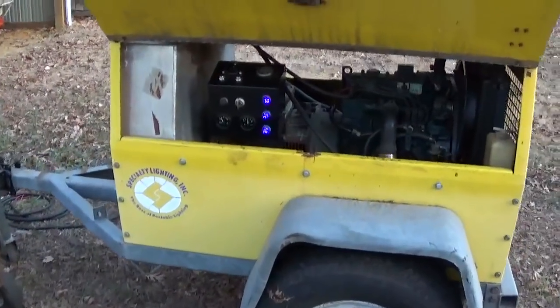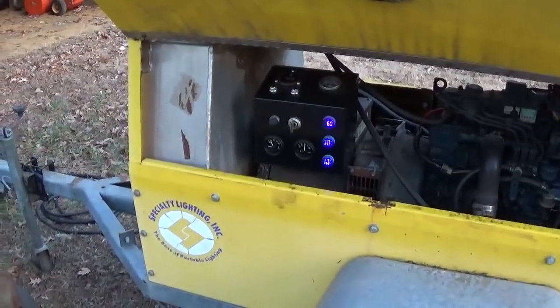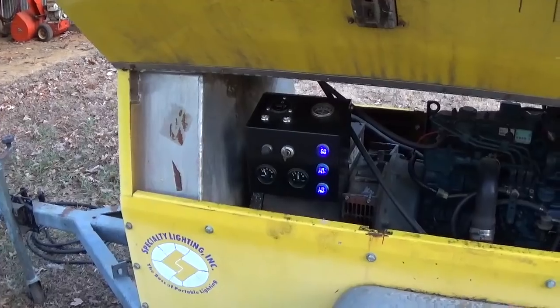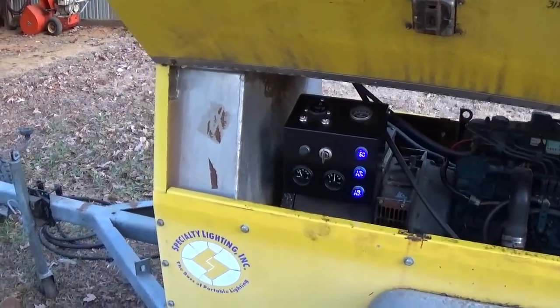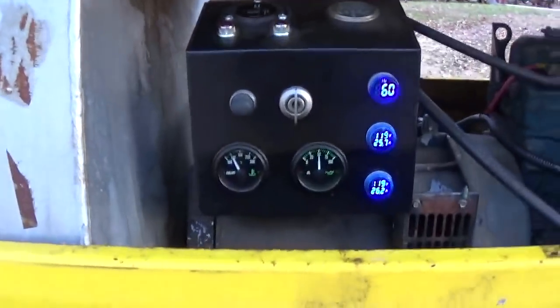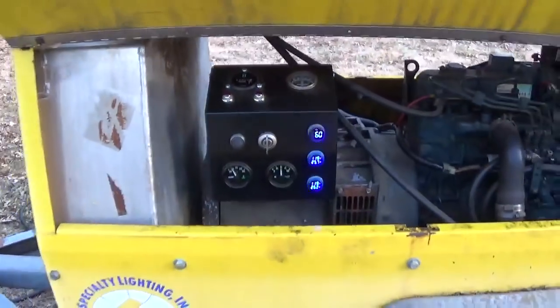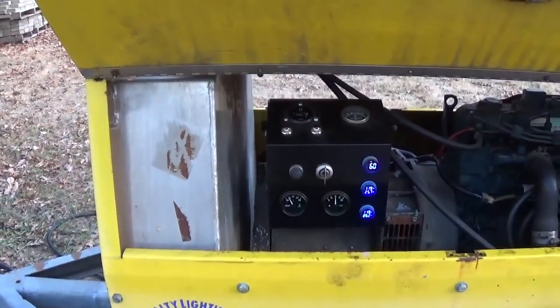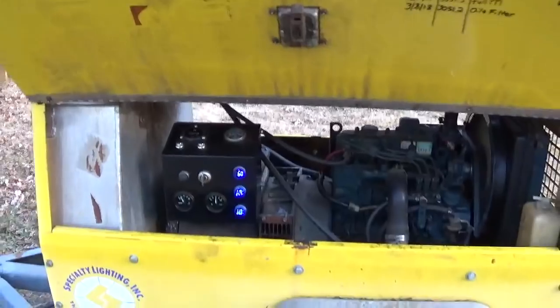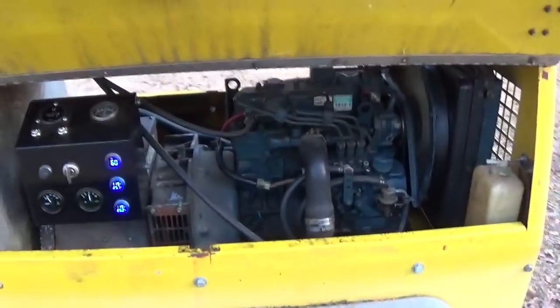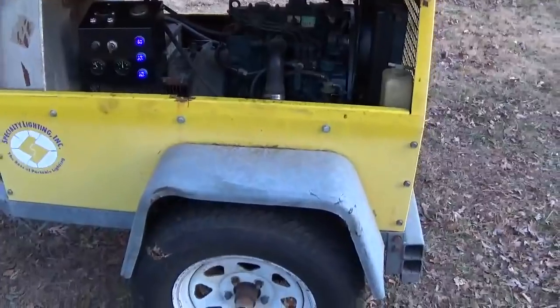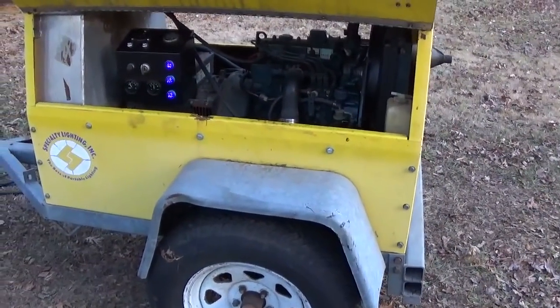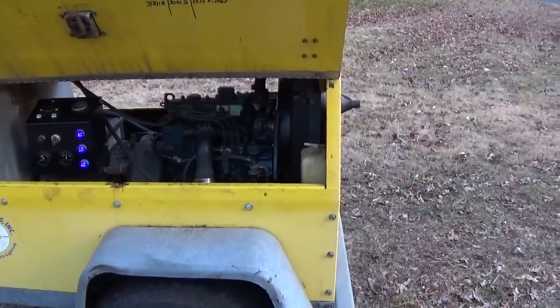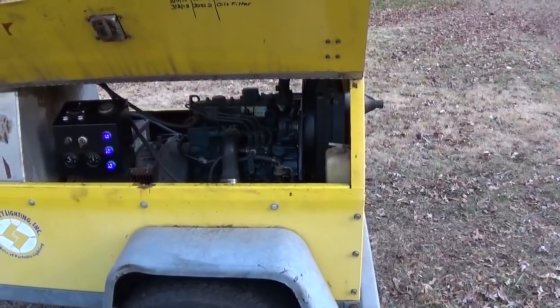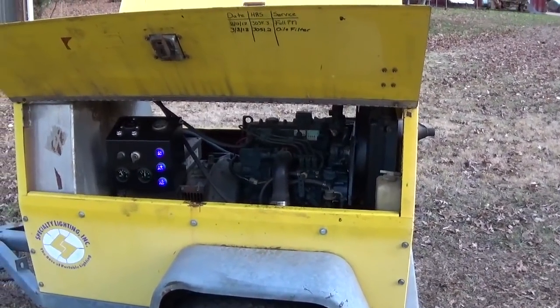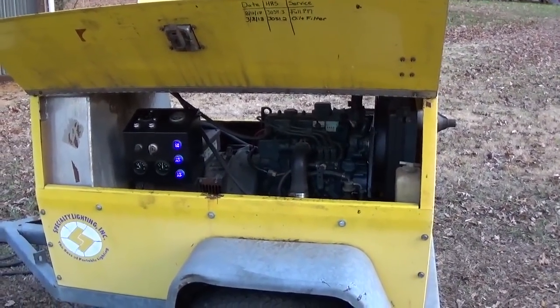Well, we've had a good half hour at 100% load, about 26 amps per leg. We're holding about 50 pounds of oil pressure hot. The temp gauge only got up to 140, which is actually a bit cold. I should have changed that thermostat out when I had the thing apart, but that's very easy to do. I guess that's a project for another day, really.